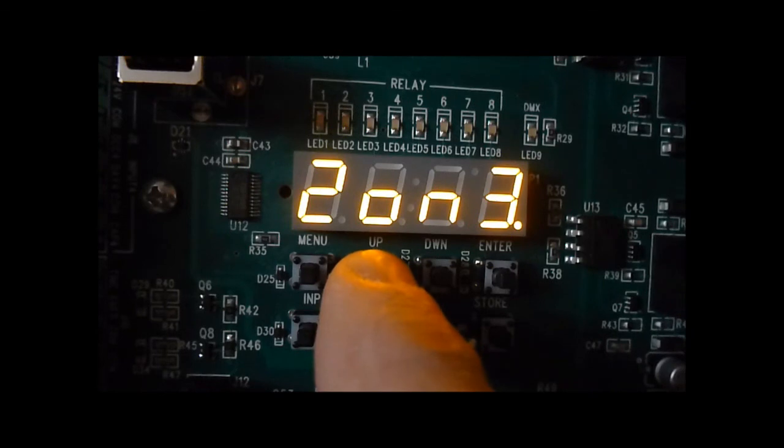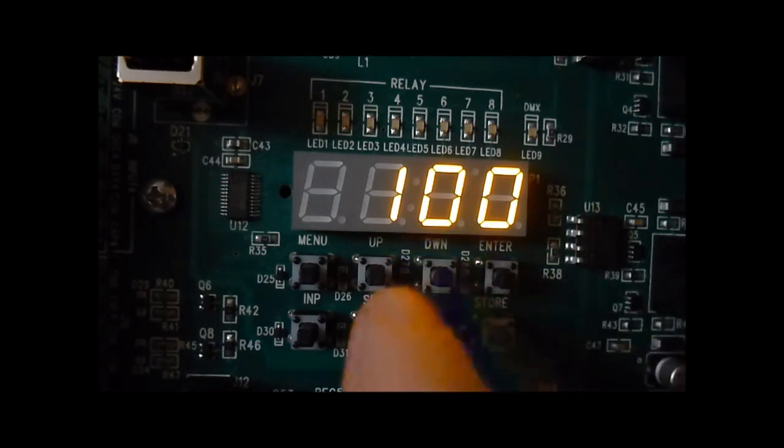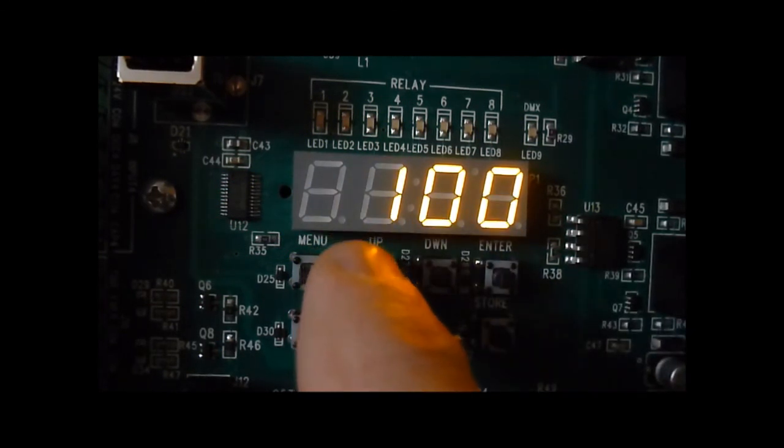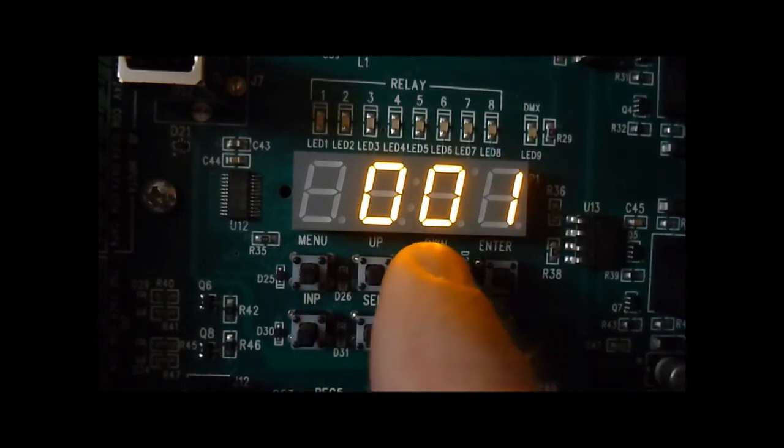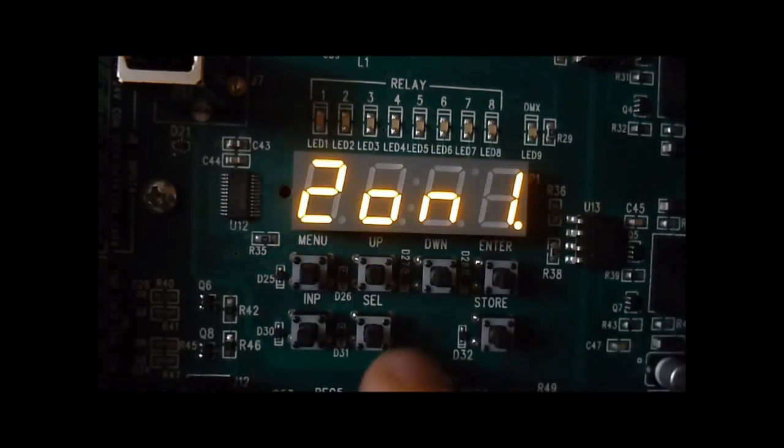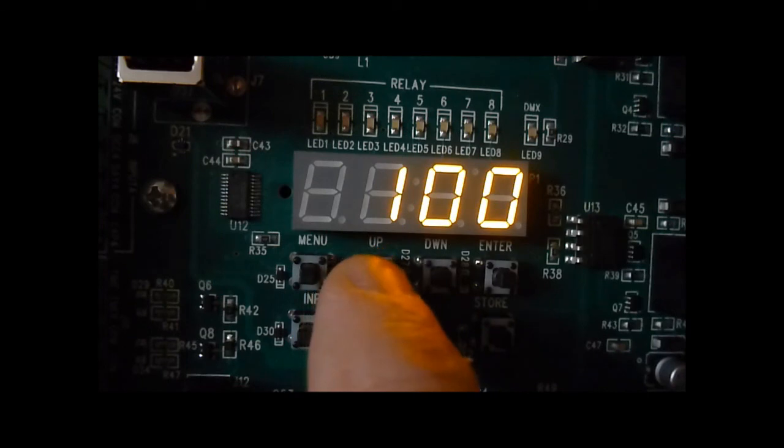Press enter. You can adjust from zero to 100 percent. By default it's set to 100 percent, which means any daylight sensor assigned to control this zone, which we chose right now with zone one, will be 100 percent affected by the scaling of the photo cell. So primary daylight zone would typically have a 100 percent setting.